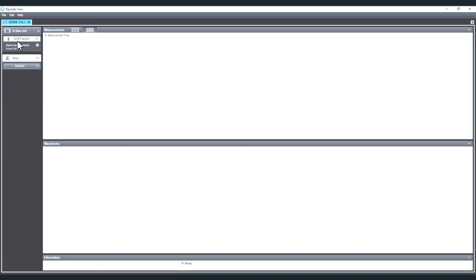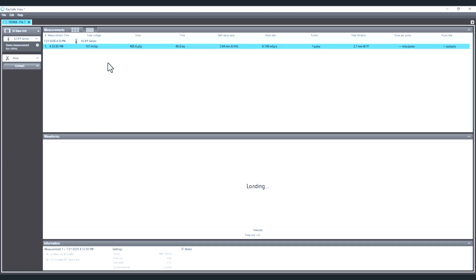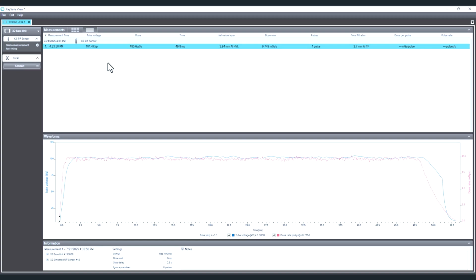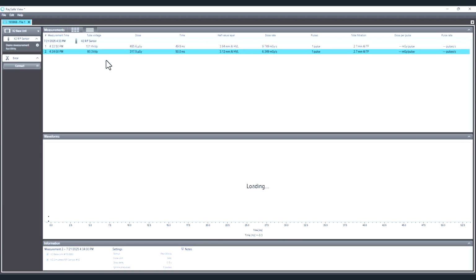Now the X2 RF sensor is in demo measurement mode. We're going to simulate a measurement, and you'll see data populate along with the waveform visual. I'm going to do a 100 kVp exposure, and there we go. I'll do another one, this time an 80 kV.